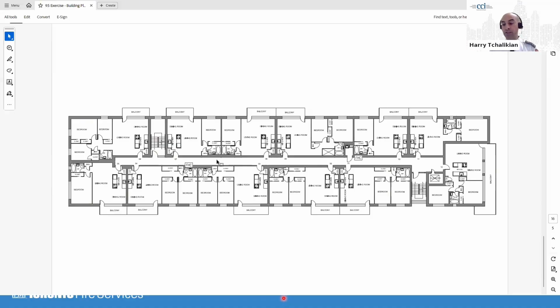This needs to be addressed on a case-by-case basis with more complicated HVAC systems. Do you have hot air blowing into the corridor or suite? Yes. Is it electric? Then no. If it's 100% electric, but you have a fan blowing over an electric heating element, the heat exchanger is electric fully, no, you don't need a carbon monoxide alarm.